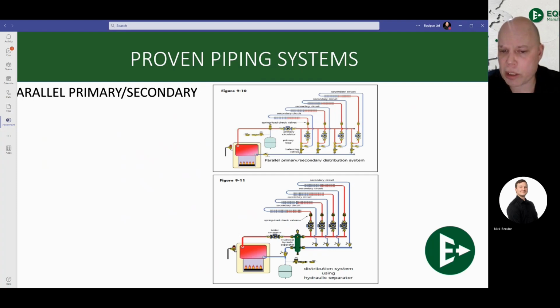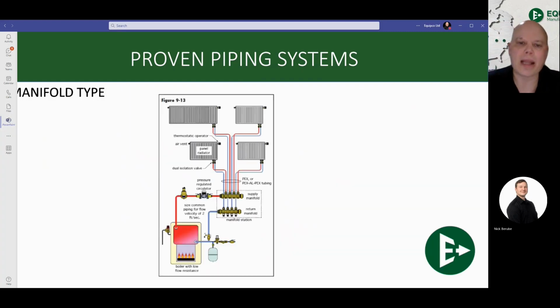Extremely easy to service because we know that the boiler is always going to get the flow that it needs. The system's easy to service because it's just a series of pumps. If the pumps are working, great, so is the system. If the pumps stop working, now your system has stopped working. So really easy to diagnose and to troubleshoot. And that's essentially where you are now.